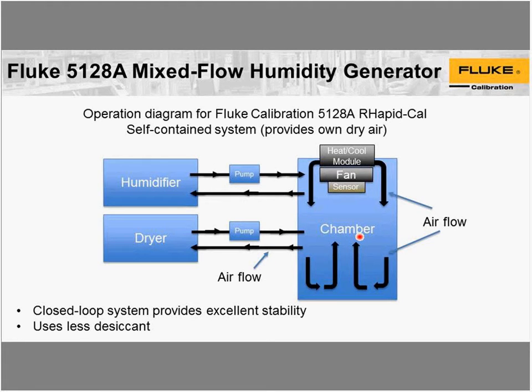What else? Temperature and humidity sensor is here in the chamber, and again, it's calibrated and provides stability, but also provides for the controller information for controlling temperature and humidity.